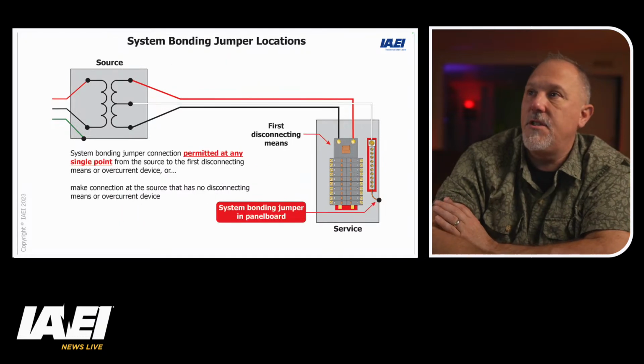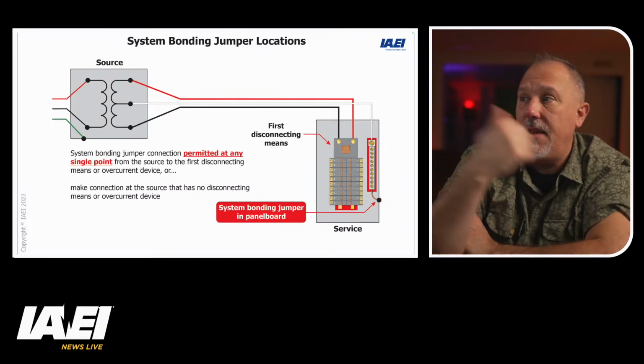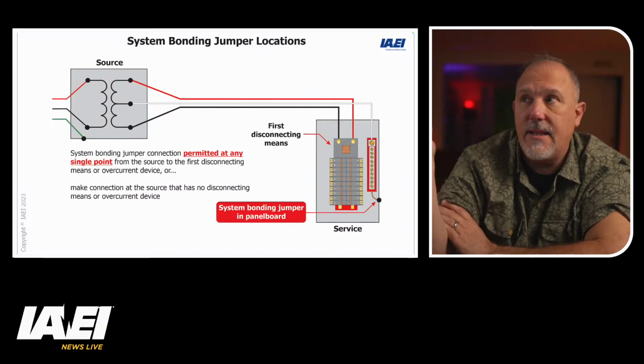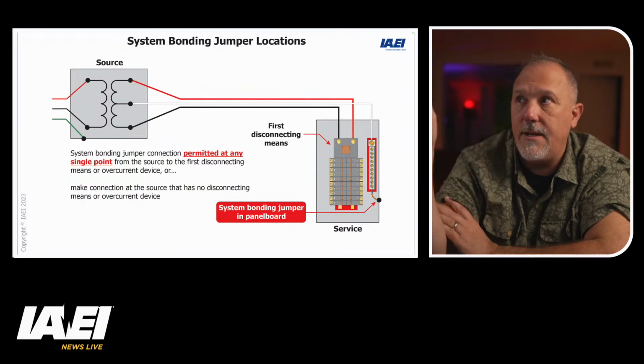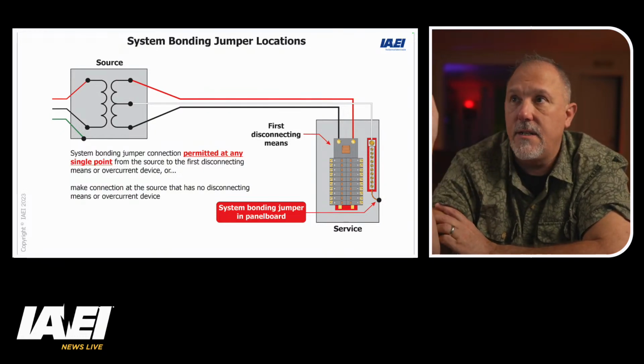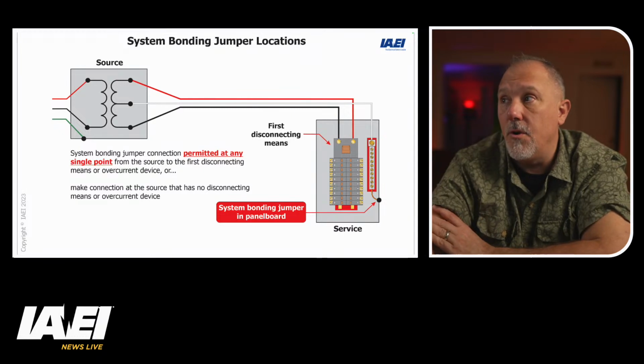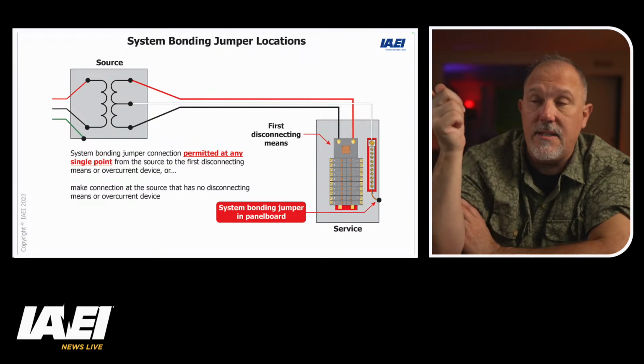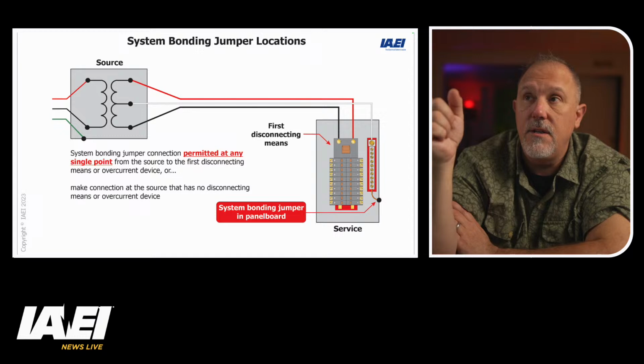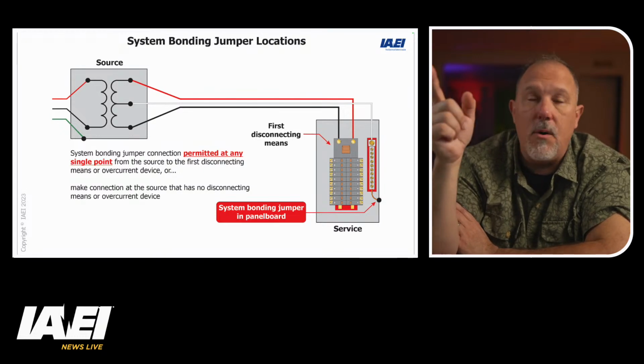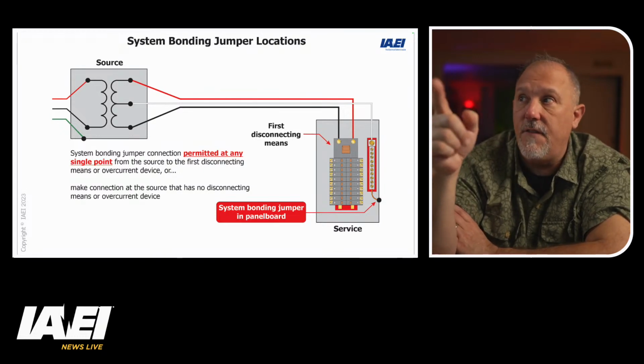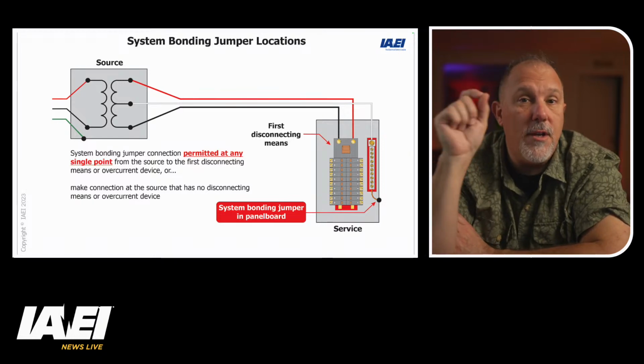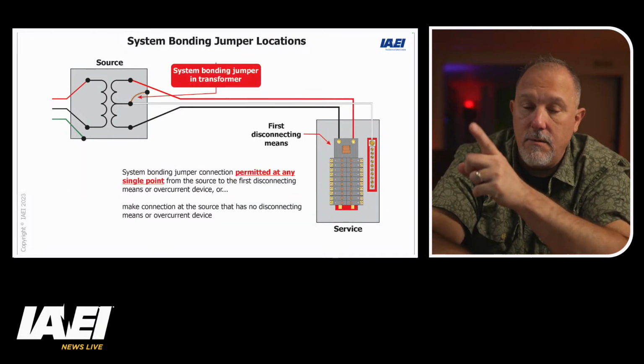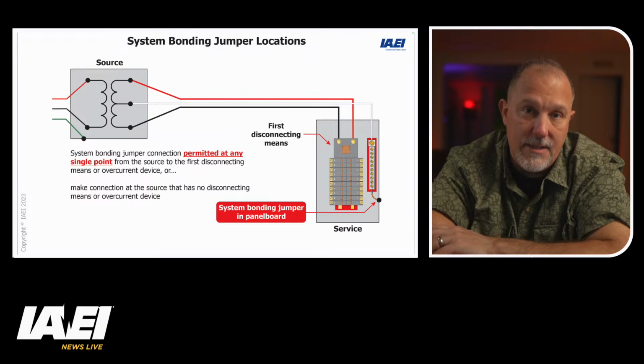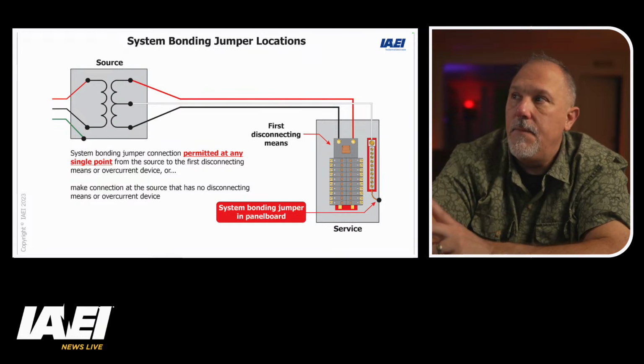I like the images. Images are worth 1,000, and then that's where you're going to bond it again at that first panel board. So you're going to bring that neutral, that grounded conductor, or you can do that here. So in this case, what they're doing is they're not establishing that bond in the transformer itself. They're doing it at the panel board. You can do it either way. You can do it there, or you can do it down at that first panel board.